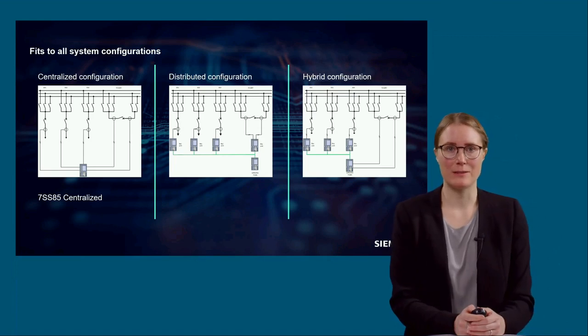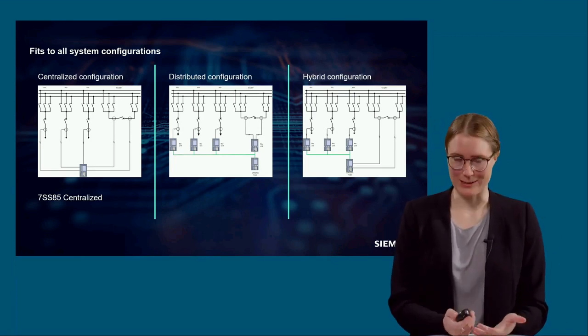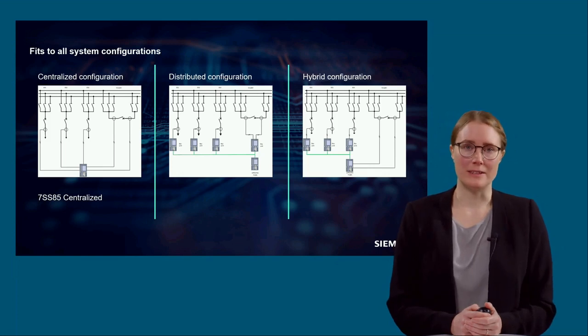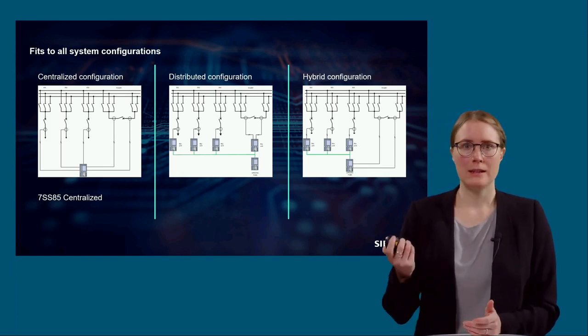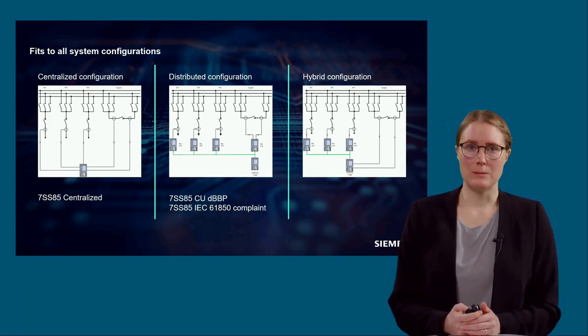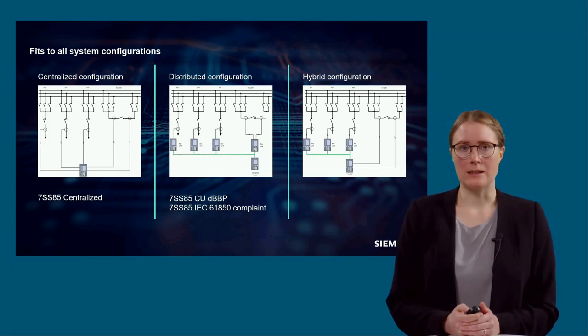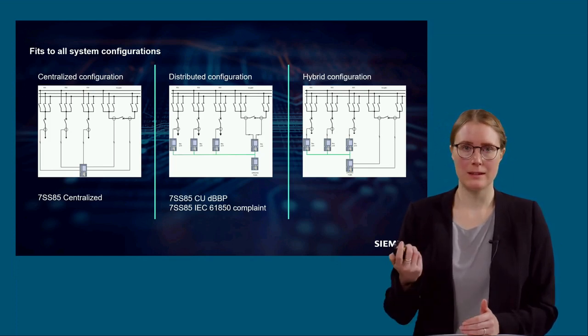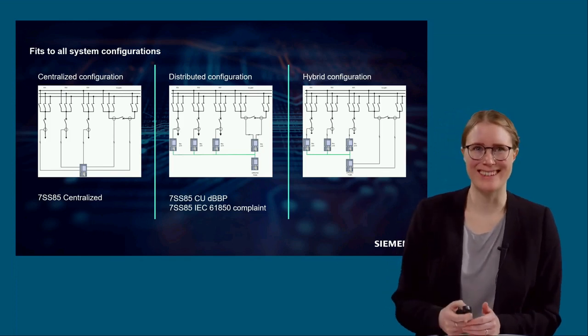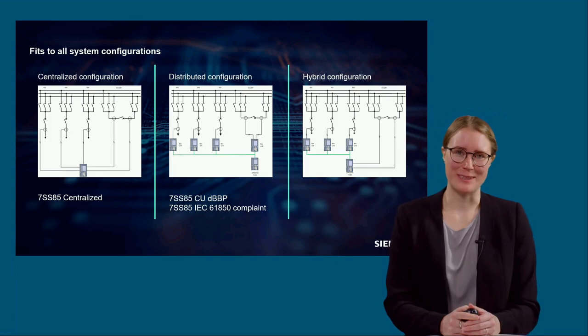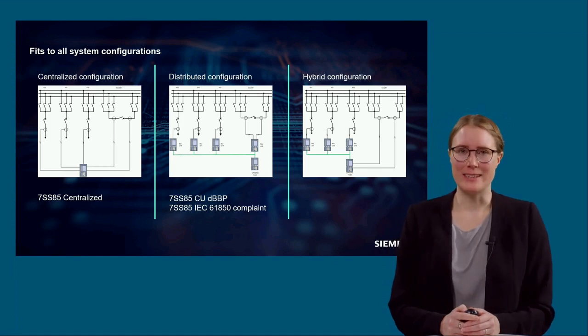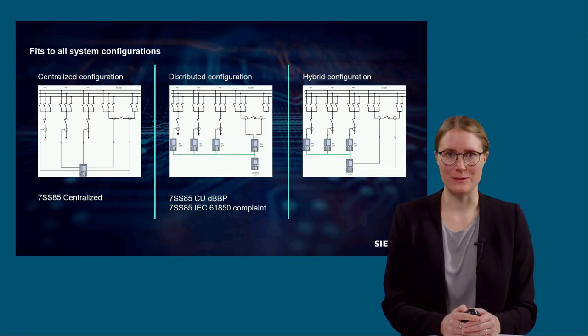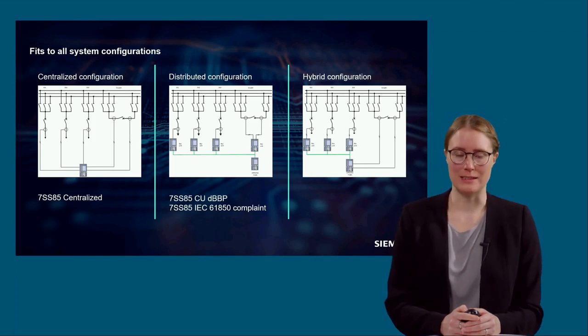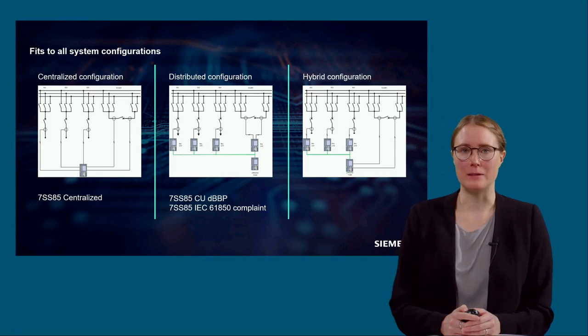For the centralized configuration, we use the 7SS85 centralized approach, quite obvious. For a distributed setup, you can use either the 7SS85CU distributed busbar protection or the 7SS85 IEC 61850 compliance solution. The IEC 61850 compliance solution is fully integrated in the overall IEC 61850 process and station bus system architecture. It is a very flexible solution, but the engineering effort is quite high.